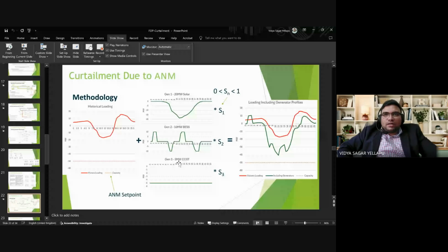This is the case of a combined cycle gas turbine. This is always exporting at 5 megawatts. All these generation sources will have an impact, expressed in terms of sensitivity factors, on the constrained assets. That means it is not required that a particular generation affects the constrained asset by 100%. Even though 100 megawatts of generation is added at one point, it may affect a constrained asset by only 20 megawatts. That is the concept of the sensitivity factor. If 100 megawatts of generation affects that constrained asset by 100 megawatts, the sensitivity factor is 1. That is the concept of sensitivity factors.